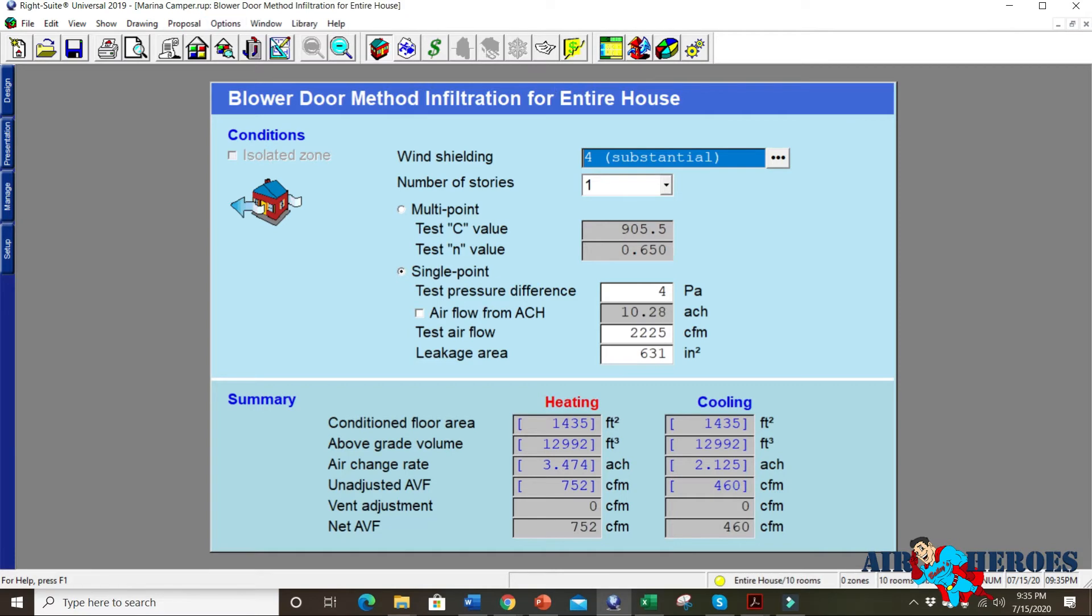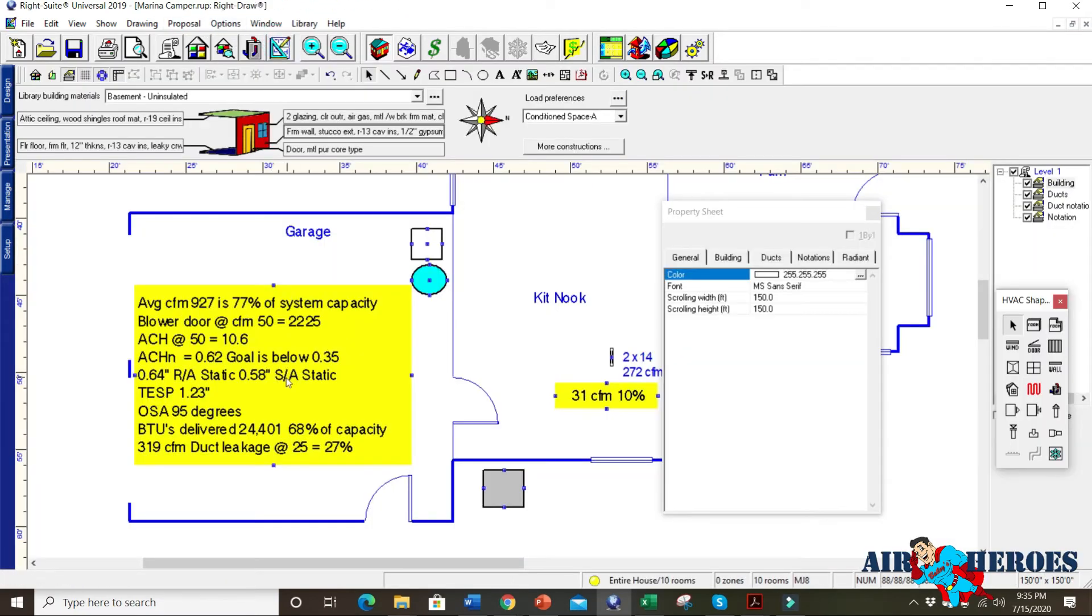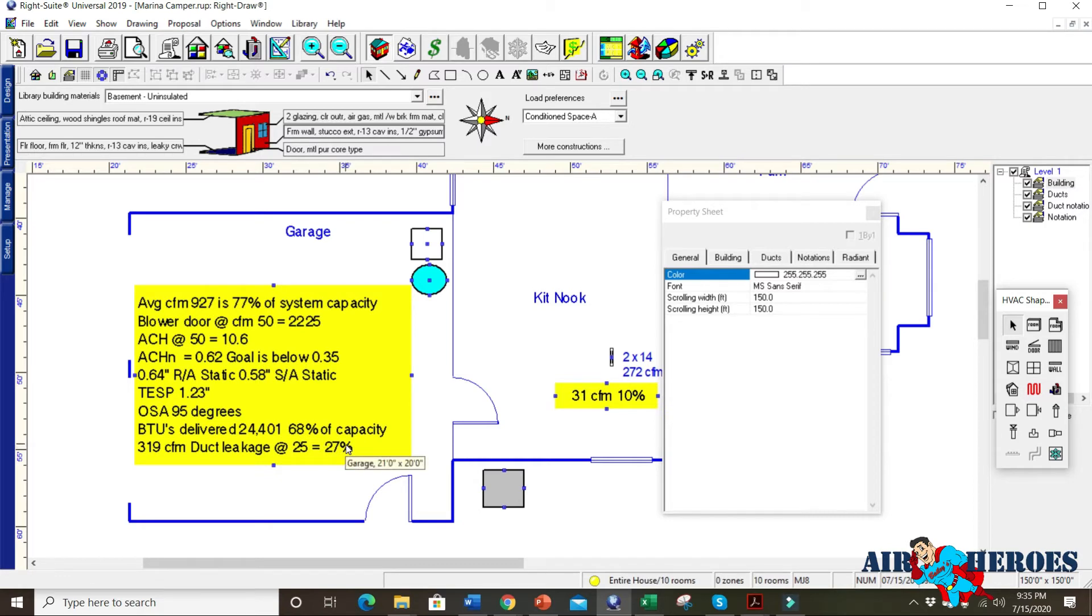So if they didn't have all the infiltration and they have duct leakage, because if we look at our duct leakage down here, they have 319 CFM duct leakage at 25 Pascals. That's 27% of duct leakage. So they're leaking a third of their air almost out of their duct work. So there's a whole bunch of stuff we have to take care of.